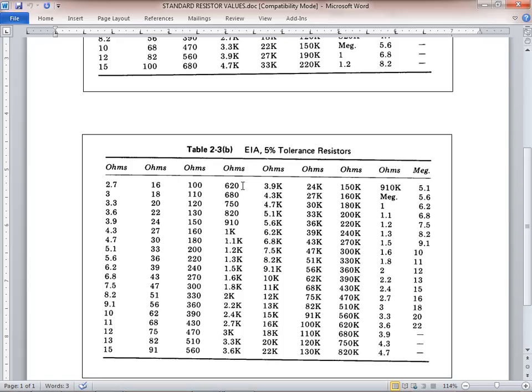I'd multiply that by 1.05. I'm sorry, I'd divide it by 1.05, right? No, that's right. I'd multiply. I multiply by 1.05, see if it came up to be greater than 640. If it does, then we'll go down to the next standard.